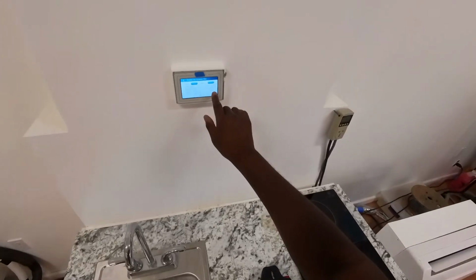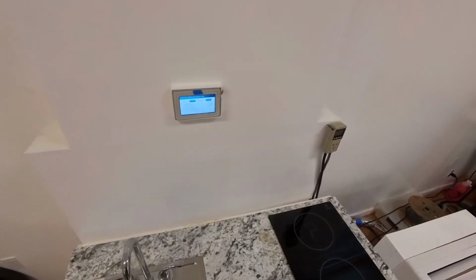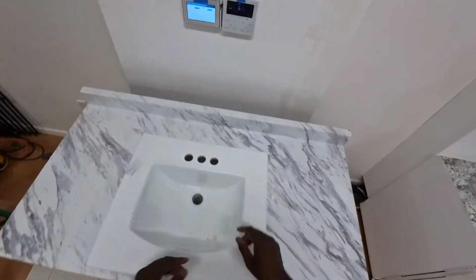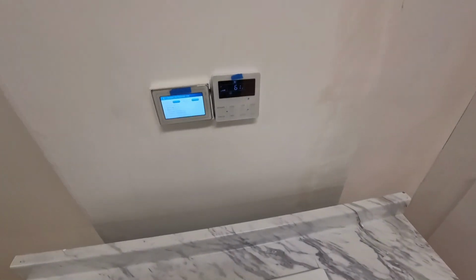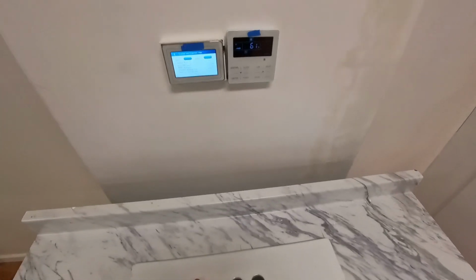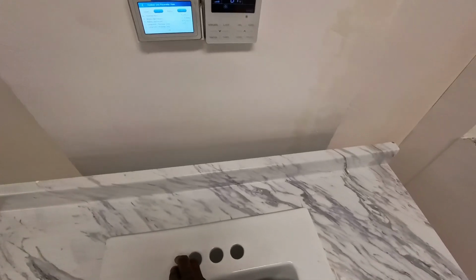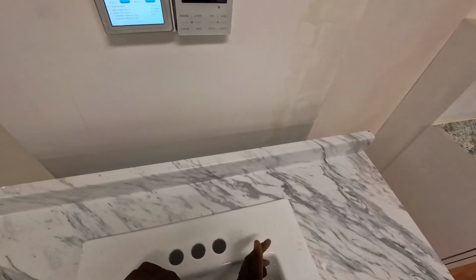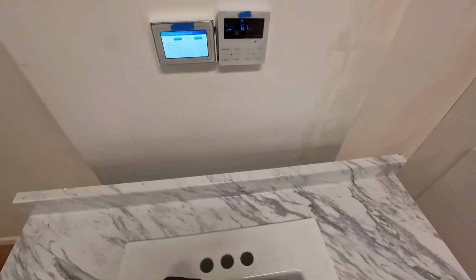If we look at our pressures here, you see my high side pressure is like 437. And then over here, my high side pressure is over 500. So what that's telling me is that there's too much refrigerant inside of this particular model right here. That's an easy fix. But this is one of the ways in which indoor heat pump will be easier for home and business owners to do maintenance on their systems.